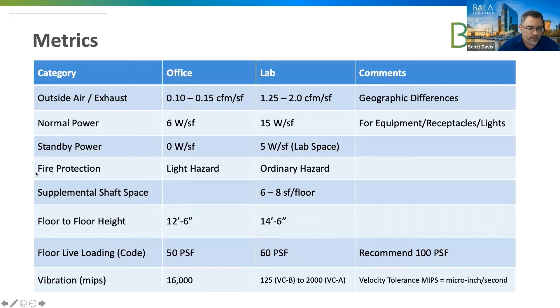Okay, next we're going to look at clean spaces and vivarium in comparison. When we're looking at clean space, we're really talking about a clean lab or a very low level clean room, ISO 8, ISO 9, which under the old federal standard was class 100,000. So it's your very entry level, introductory level type clean spaces. And for the outside air and exhaust air content, and even minimal power as well, it's pretty much equal to a lab. The difference with the clean spaces is they'll have a higher rate of air change that has to be moved through the space, but it doesn't have to be 100% outside air. It can be recirculated air.